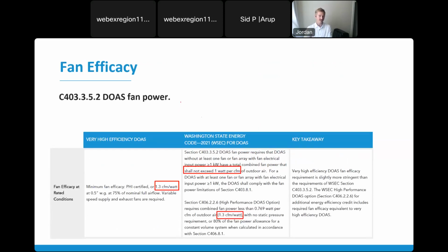How does that fan energy compare to VHE DOAS? We have landed on 1.3 CFM per watt as being the minimum fan efficacy. The base code says that you shall not exceed 1 watt per CFM, or it has to be more than 1 CFM per watt. And again, this high performance DOAS is a little bit better, 1.3 CFM per watt, which aligns exactly with very high efficiency DOAS requirements.